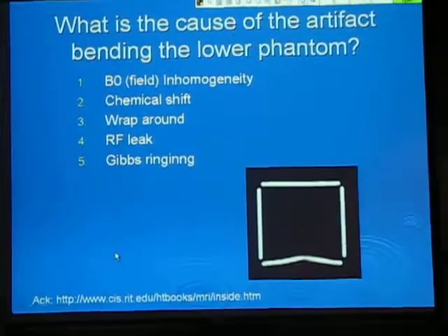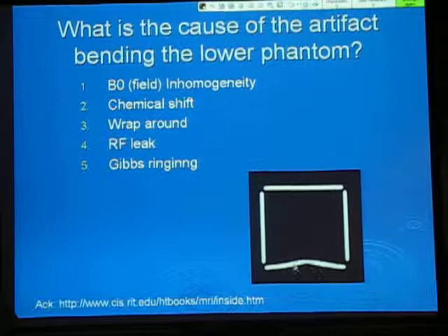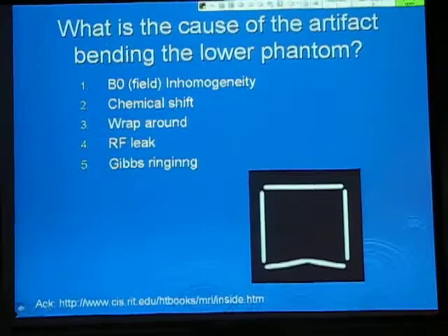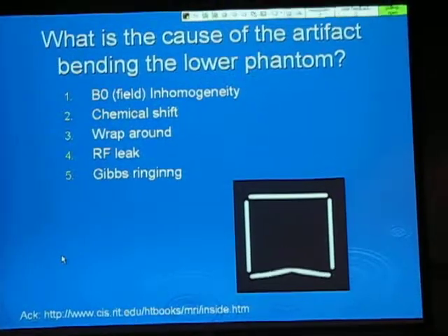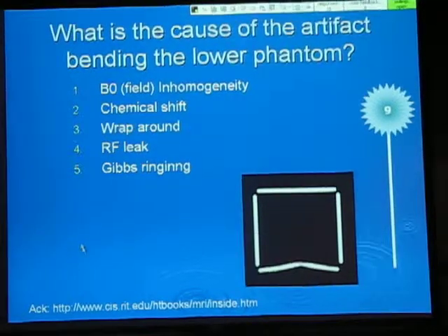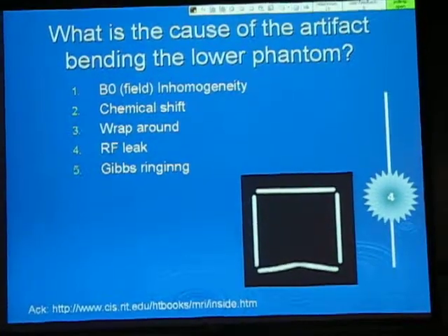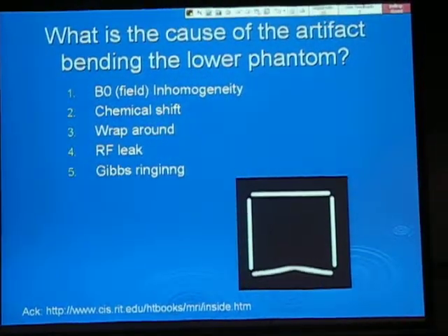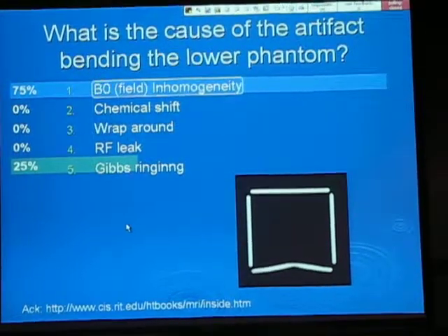Okay, next question. What is causing the bending? This is a phantom, so four rods put into the bed, and they should be straight. Why does it appear that this one is bent? What's the cause of that arc? B0 field inhomogeneity is the majority, and that is correct.